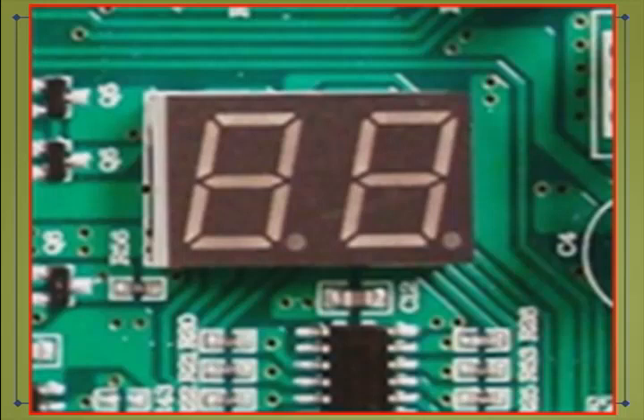There are 5 distinct speeds the system will be able to operate at during either mode. The interface control board will display a 2-digit error code in addition to an operational code to help aid in troubleshooting for technicians in the field. The interface board will also control the reversing valve. The valve is still energized in the cooling mode. The voltage will come from the O terminal on the interface board.